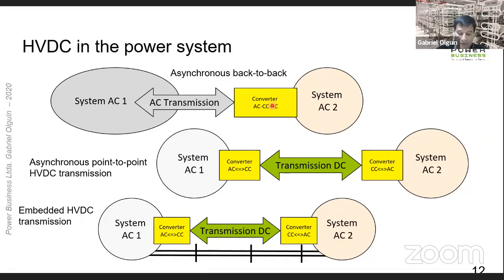In a back-to-back interconnection, the rectifier and the inverter are located at the same place to exchange energy between two systems that, although having equal frequency, cannot securely be interconnected due to stability issues. A back-to-back HVDC can also enable interconnection of systems with different frequency, and no line is needed since the rectifier and the inverter are located at the same place. An embedded HVDC link interconnects two areas of a power system. An embedded HVDC link has a big impact on the stability of the system, since by controlling the massive power through the HVDC link, the power in the rest of the system is also affected, making it possible to better exploit the existing AC transmission grid.